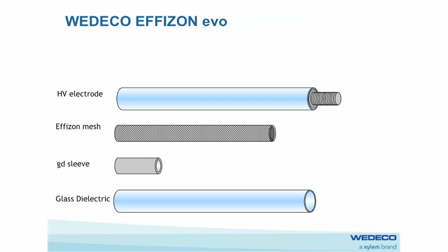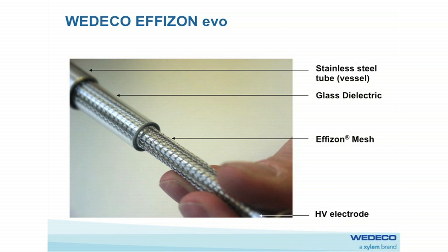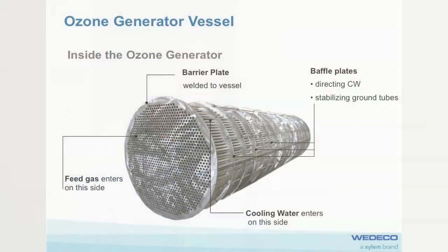The electrodes are about 1.5 meters in length, and about, you can see in the next slide, the diameter. They're quite small, a little bit thicker than my finger. They're also much smaller than the ceramic electrodes, which means we can get more electrodes into a single body, producing obviously more ozone, which is why we have the world's largest ozone production systems. So basically it's a big shell and tube heat exchanger.